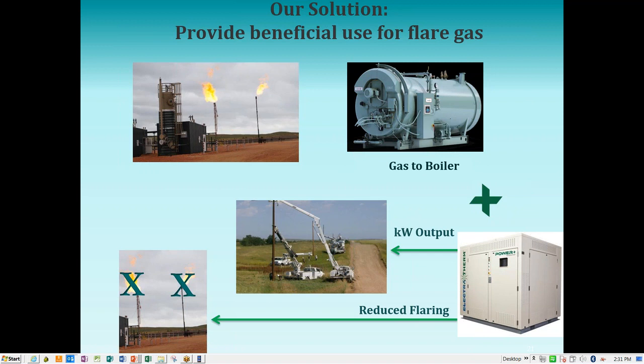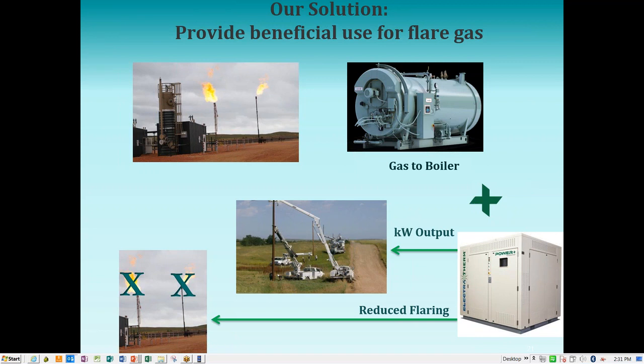Hey Loy, let me add something. As people may know with the flaring issue, those flares are variable - they vary with time, liquid content, BTU content, H2S content, etc. The boiler is a very robust design and can take raw gas or treated gas with the same burner. As Loy described, we picked a 30 ppm NOx burner. So all the challenges the flare gas presents - just like at a wastewater treatment plant with siloxanes and everything else - the industrial boiler takes on the hard work for the site dealing with that flare gas. Then the Power Plus basically has a hot water loop running through it. So all the work is done by that 100-year-old technology, which is great.